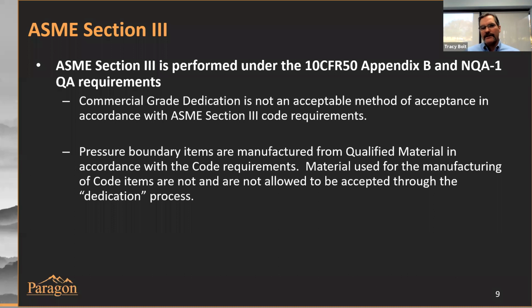In regard to Section 3 items, you have to have a 10 CFR 50 Appendix B program, and the code actually requires that you utilize NQA-1 in order to meet those requirements. Commercial grade dedication is not an acceptable method of accepting items or material for code items.